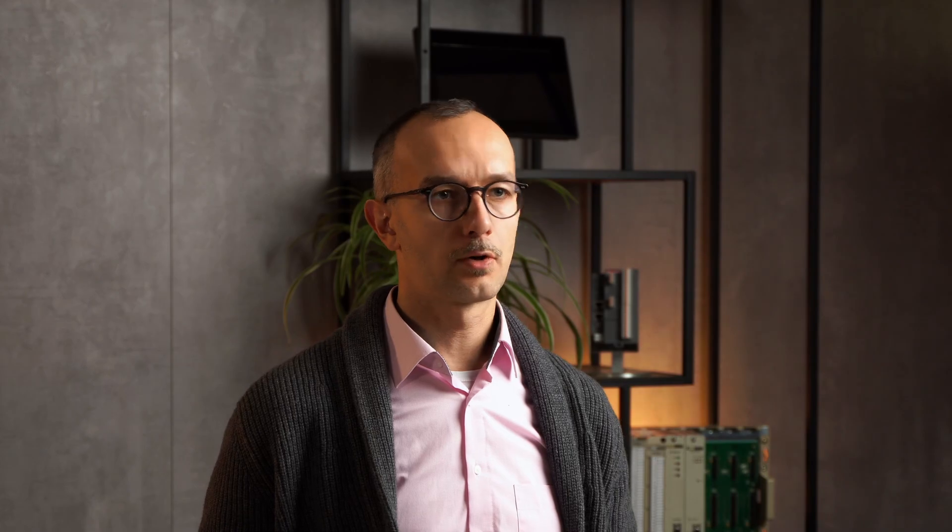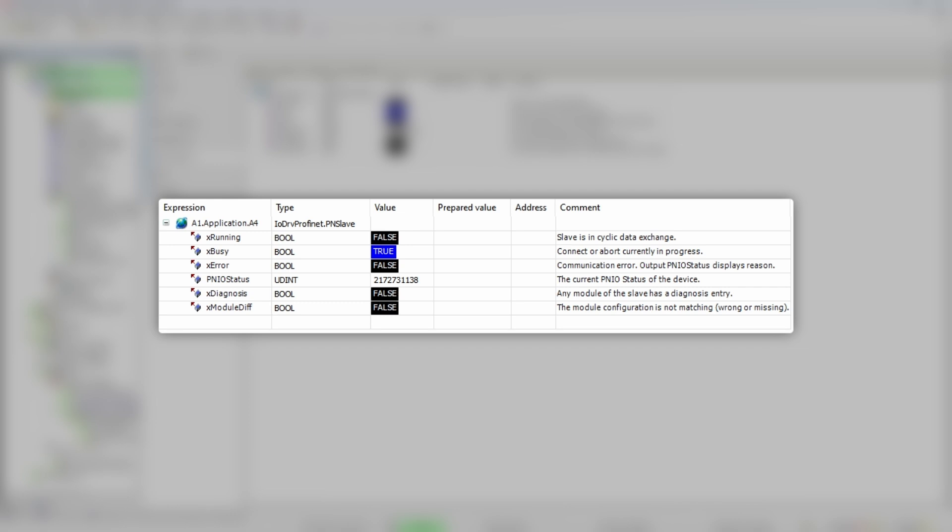In PNIO IEC Objects tab, there is a structure which has the same name as the ProfinetIO device, A4. The structure has a child boolean variable x running, which does exactly what the name suggests. It turns true when communication is running. Now we just need to take that flag into account in the part of the program where we handle analog I/O scaling.